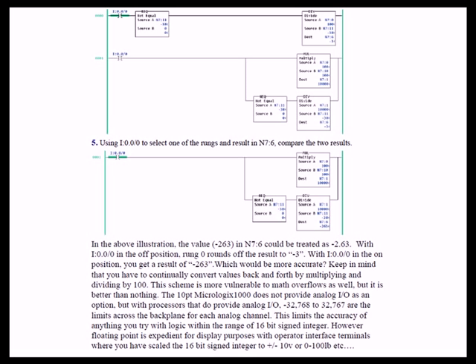Now the 10-point MicroLogix 1000 does not provide any analog I/O as an option. But with processors that do provide analog I/O, you are still limited. That is, with 16-bit backplanes, you are still limited to signed integer minus 32,768 to a positive 32,767. These are limits across the backplane for each analog channel. And this is going to limit the accuracy of anything you try to do with logic within the range of 16-bit signed integer.